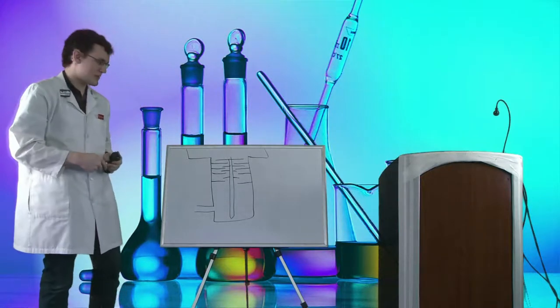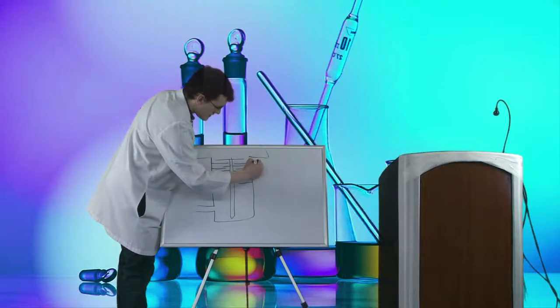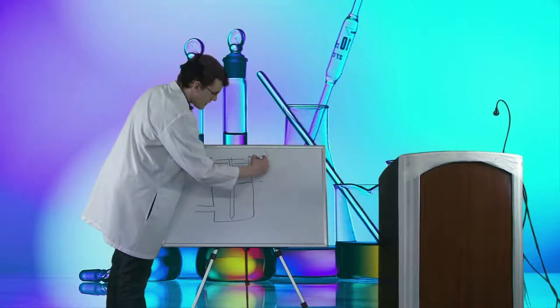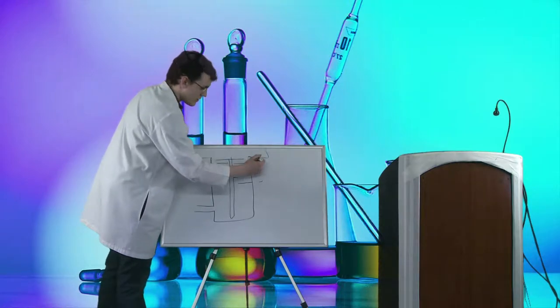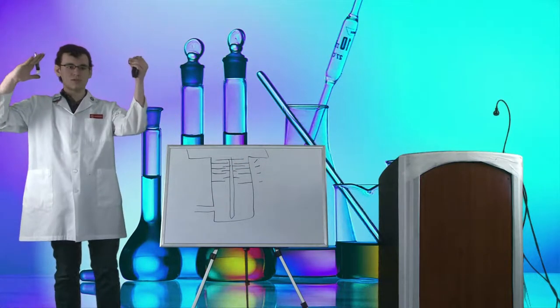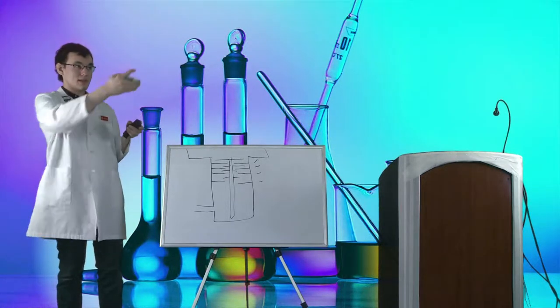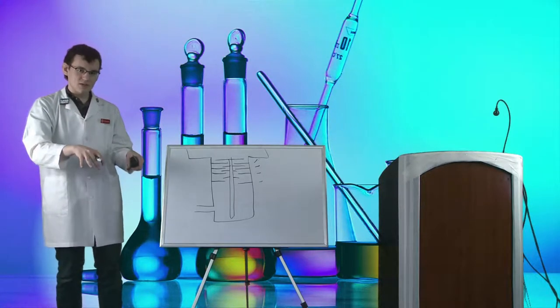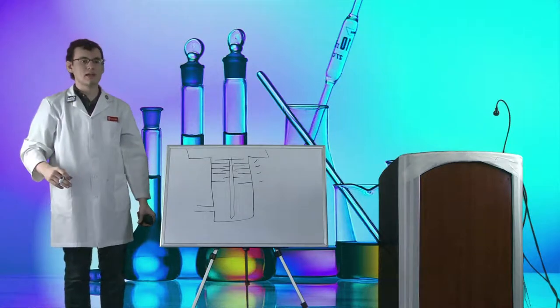The blades are all at different angles — at the top they're at a very steep angle, and as you move down the pump the angle gets flatter. When an air molecule flows down into the pump, the blade spins around and hits the air molecule. Because we're hitting an object with a 45-degree blade, it knocks it downwards. This isn't like a regular fan slowly moving through fluid air — this one slams into molecules at high velocity, imparting kinetic energy to force them down into the pump.